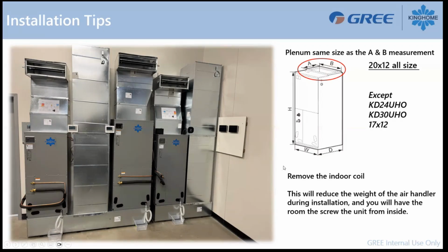Also, another little tip that I can give you is, just before you do your installation, you can remove the indoor coil. You just have to remove a couple of screws here and remove the panel. Then you will have access to the coil. You can remove the coil. That will reduce the weight of the air handler during the installation, and also that will give you enough room to screw the unit from the inside. So this is really perfect to do the installation when you have a bed like this under the unit. And also it's much lighter to manage the air handler and to install it.